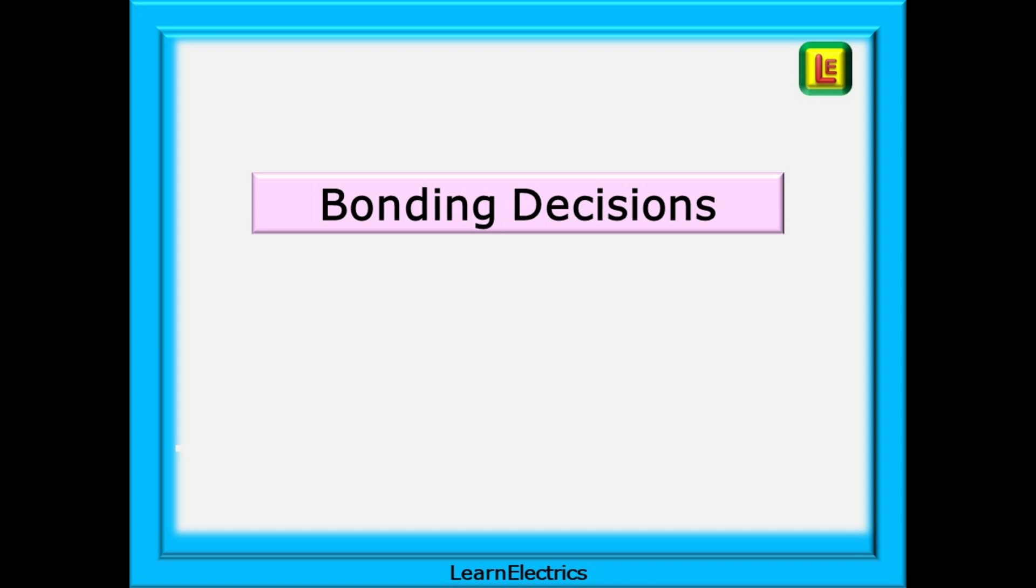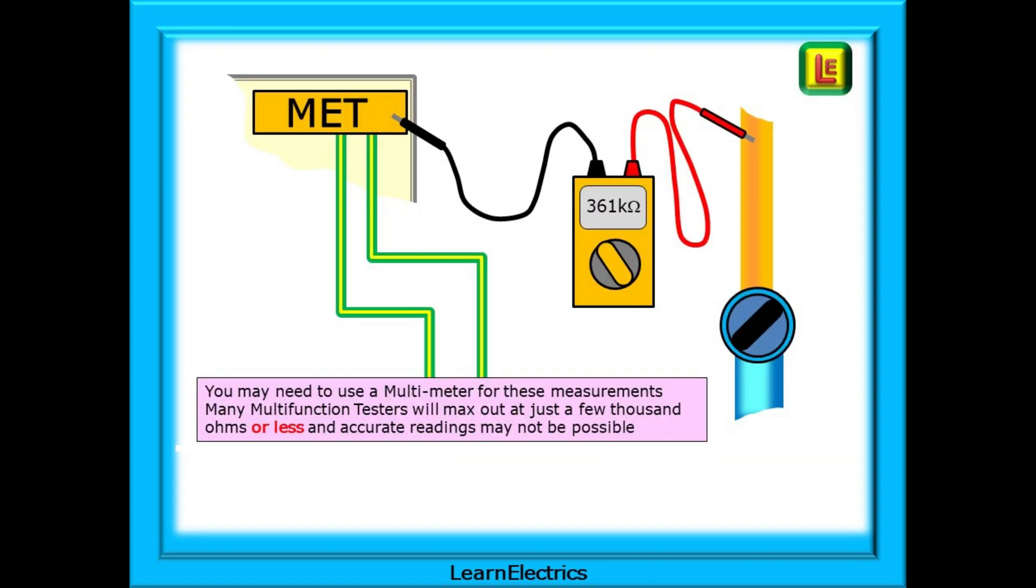So how do we make decisions about bonding or not? We should measure the resistance between the main earth terminal and the conductive part being tested with a multimeter that has sufficient ranges that it can display the resistance values accurately. Many multifunction testers will reach their maximum display value at just a few thousand ohms or even less, and accurate readings may not be possible. A reading such as OL shows that the reading is over limits for the meter, and that is not going to help us to make a decision.